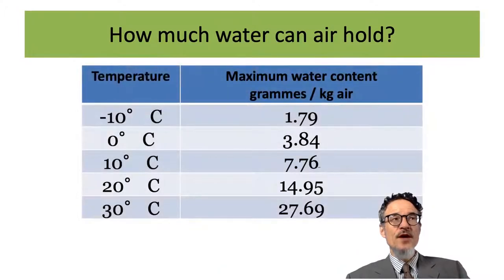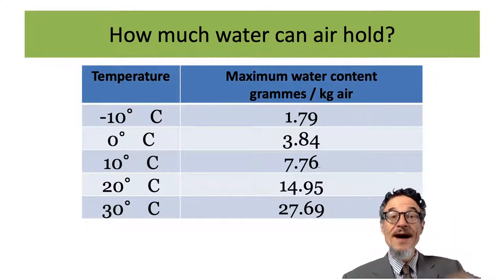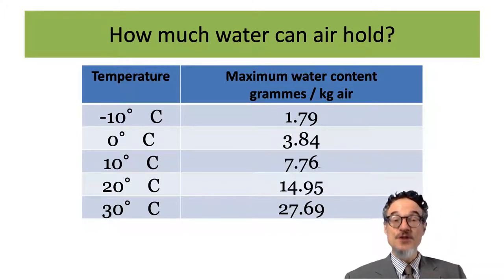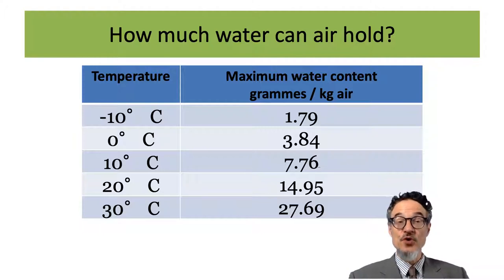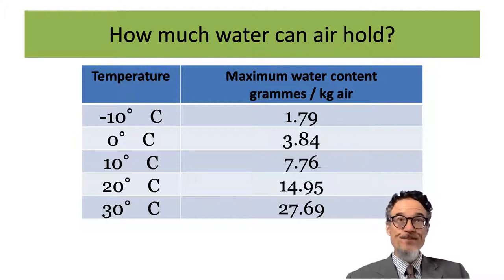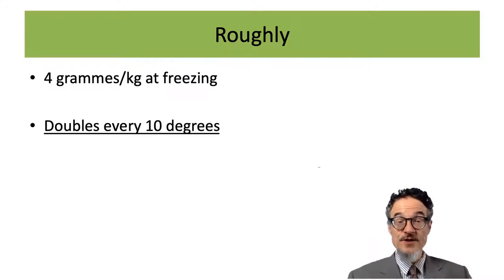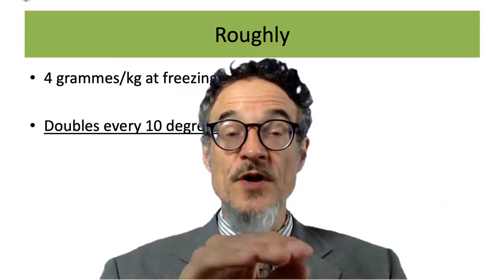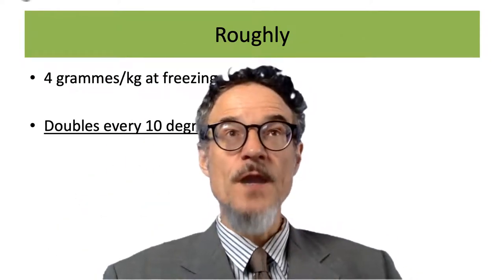For temperatures in and around buildings, we're usually in a range from about minus 10 to plus 30 degrees centigrade. Very roughly, at freezing point it's about 4 grams per kilogram, and every 10 degrees it doubles. So if you go 10 degrees warmer it's twice as much, another 10 degrees it's twice as much again, and so on.